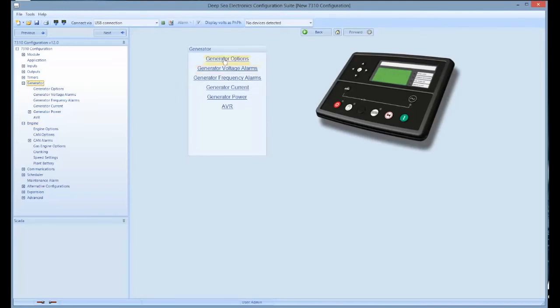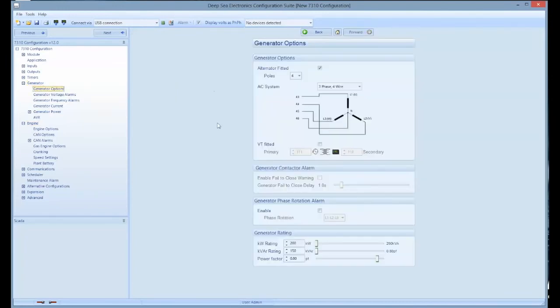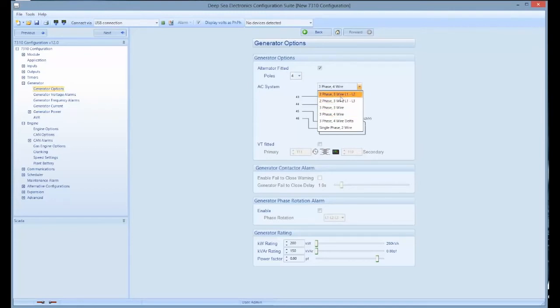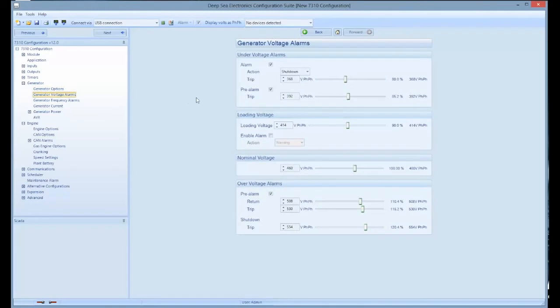For example, when you click on generator options, you can convert a generator from single phase to three phase. By clicking on generator voltage alarms, you can change under voltage, over voltage, and nominal voltage readings.